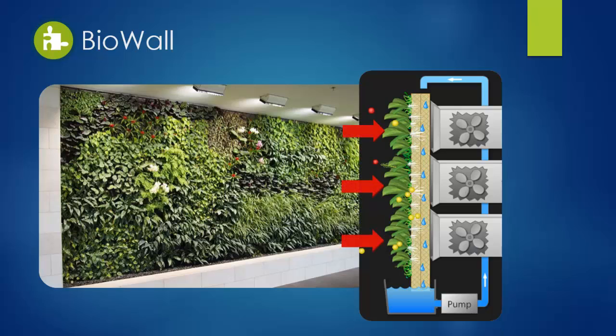When the air goes through the wall, the plants will capture excess carbon dioxide and 80 to 90% of volatile organic compounds, which meet ASHRAE Standard 62.1 2010 Table B1 to allow ventilation to be reduced to what is needed for building pressurization.